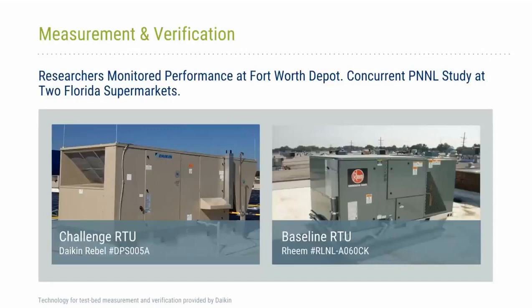However, this approach takes twice as long to complete and also requires more resources. We didn't have either of them. So we used an alternate approach to verify the performance of these new high-performance units and compared them to existing standard units. The alternate approach provides reasonable results if you're trying to compare efficiencies of 2 units. So that's what we did, basically simultaneously measure the performance. So next slide, please.